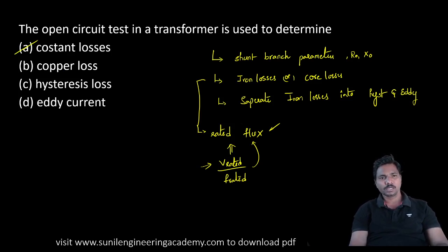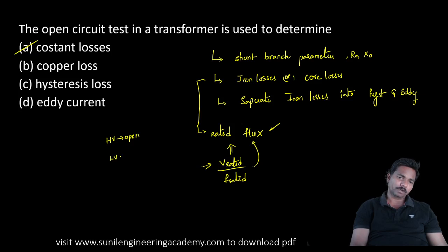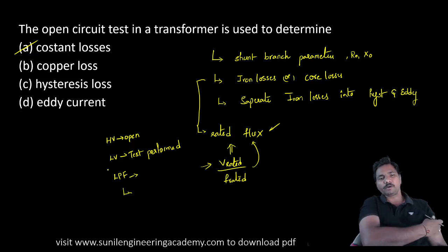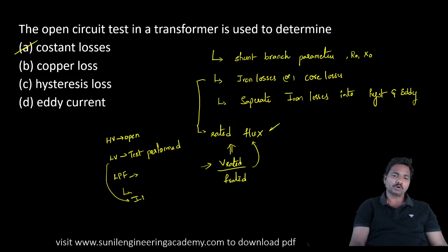This open circuit test is generally conducted by keeping HV open and the test performed on LV side. Why? Because the voltage requirement is less, the meter requirement is less. Low range wattmeters are enough, and a low power factor meter is used. If the test is performed on LV side, low voltage means current is more, then I naught is sufficient to measure. So we have the availability of meters to measure this I naught. So here the answer is option A.